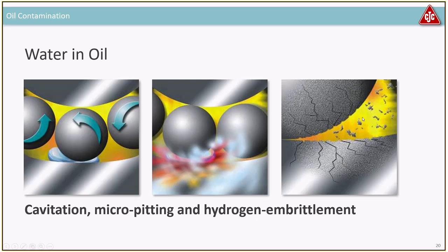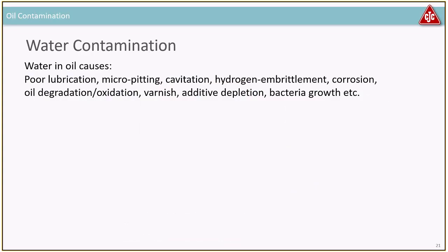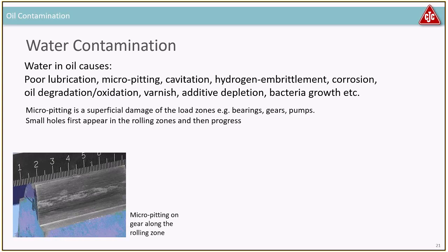Hydrogen embrittlement is another issue: water is H₂O, and when hydrogen migrates into the steel it becomes brittle like glass. A gear tooth under shock load can break because it's so brittle — gear teeth need to be ductile, not brittle. Water will also cause corrosion, speed up oil degradation and oxidation, and deplete additives. Many additives are polar and can be washed out by water — ZDDP, for example, can be destroyed by water. You can also create bacterial growth if there's enough water.